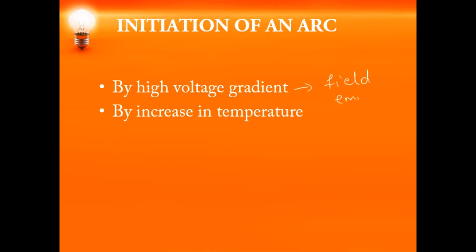Overall, when the contacts get separated, the electrons get liberated from the cathode and move towards the anode. While they are moving towards the anode, the medium present between the contacts gets charged. That is nothing but the arc formation. When the path is getting ionized, the temperature becomes more and more, and the electron liberation also becomes more and more.